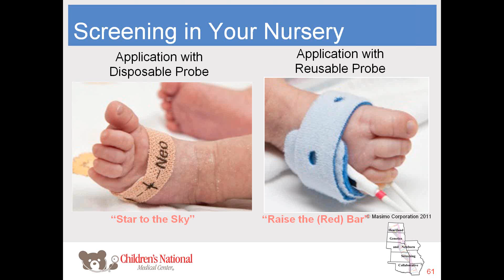If you're using a reusable probe, there may be a red bar or another symbol to indicate which side goes up. We like to use little reminders like "star to the sky" or "raise the red bar" to help providers remember. The side of the probe that's the photo detector should be placed directly opposite of the red light emitter on the fleshy portion of the hand or the foot. To accurately obtain the oxygen saturation, the two sides of the probe need to be directly opposite of one another.